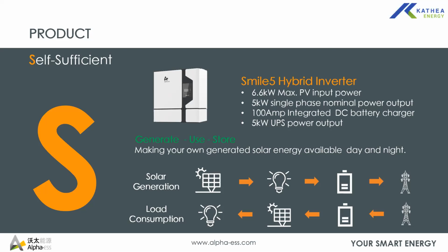However, on the non-critical side, you can have as many loads as you can. The inverter will simply supply those loads when it has excess PV. We'll also look into that in the operation modes. It has an integrated 100 amp DC battery charger.